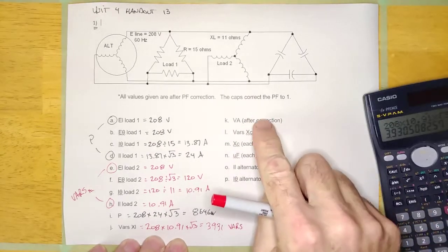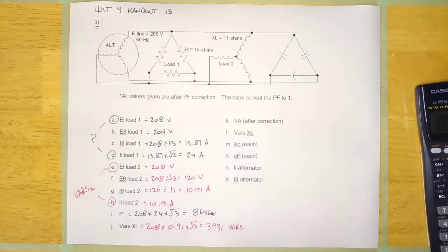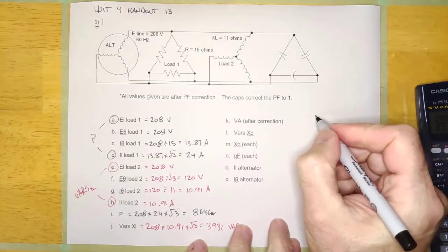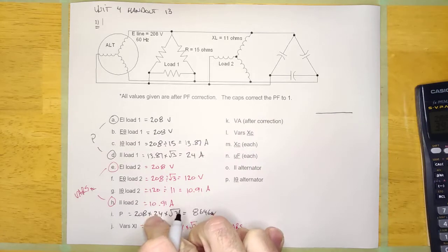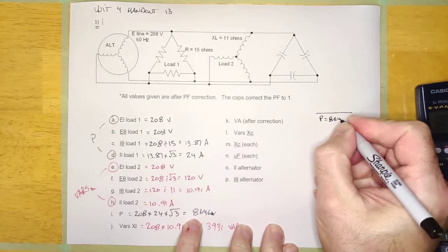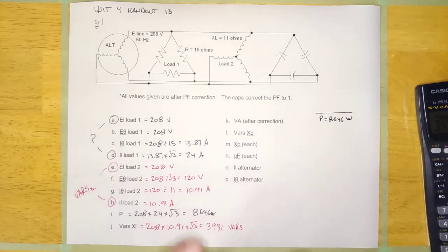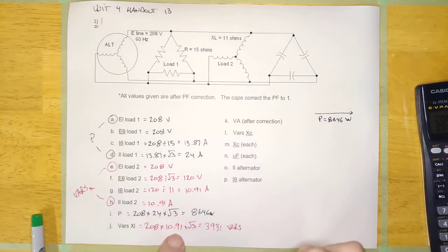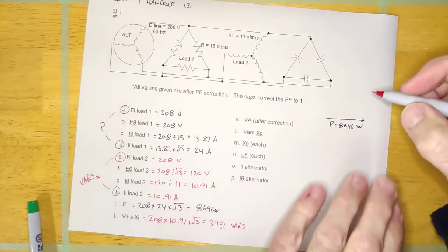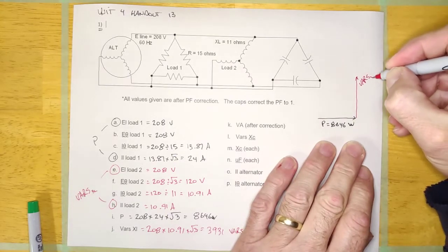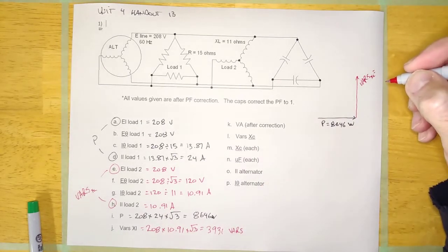VA after correction — this thing is going to get corrected to unity. Let's draw a power phasor diagram. We're going to have our true power, which we figured out: 8,646 watts. We're also going to have the inductor sitting right here as vars XL, and it looks like it's 3,931 vars.